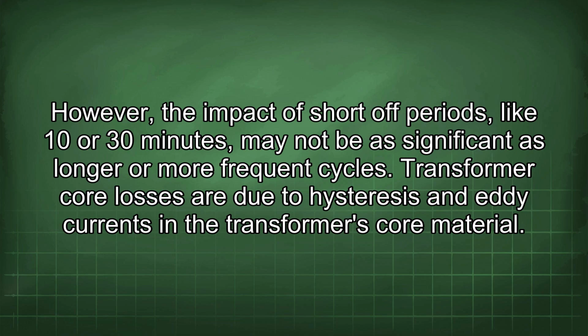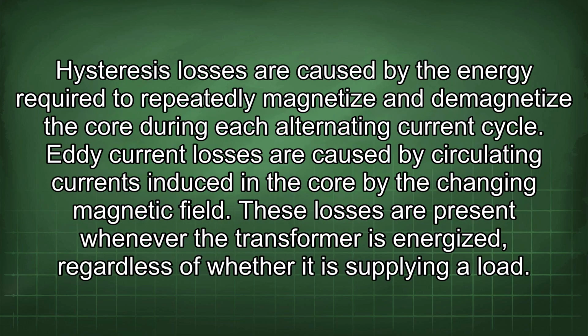Transformer core losses are due to hysteresis and eddy currents in the transformer's core material. Hysteresis losses are caused by the energy required to repeatedly magnetize and demagnetize the core during each alternating current cycle. Eddy current losses are caused by circulating currents induced in the core by the changing magnetic field. These losses are present whenever the transformer is energized, regardless of whether it is supplying a load.